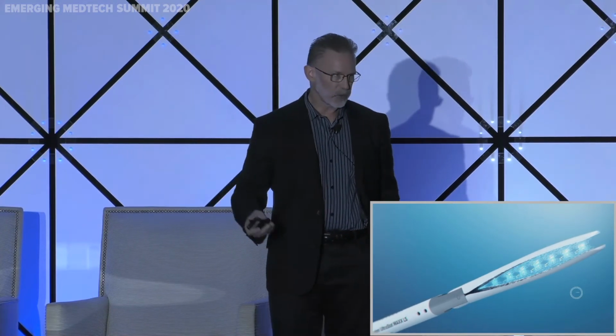As you can see, right in the center of the zone, you get an area of high intensity. This is what cauterizes the tissue. So we increase the resistance by cauterizing the tissue in the middle of it, and then that cauterized area causes the ultrasound waves to back propagate to the surfaces of the end effectors itself. So this is actually a more efficient way of doing cauterization of tissue, which ends up in less thermal damage, less thermal spread. We're electrically neutral.